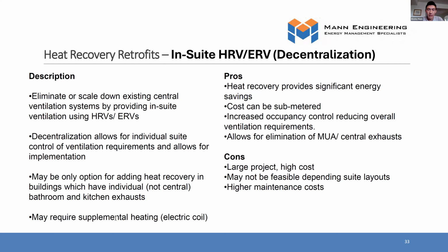Another option for ventilation retrofits is going to individual suite HRVs or ERVs. This is decentralizing the ventilation system. If you have in-suite exhaust fans already, then you're halfway there. You can install in-suite ERVs to provide fresh air directly to the suites. And then the makeup air unit itself could potentially be eliminated, but more likely just greatly downsized so that it only has to serve the corridors, and it's not having to serve all the suites as well. Because the main purpose of the makeup air is, one, to provide ventilation, fresh air, and two, to make up the air that's lost through the exhaust systems in the building.